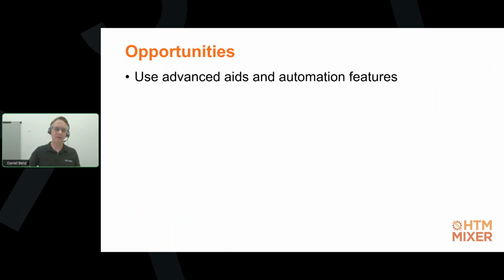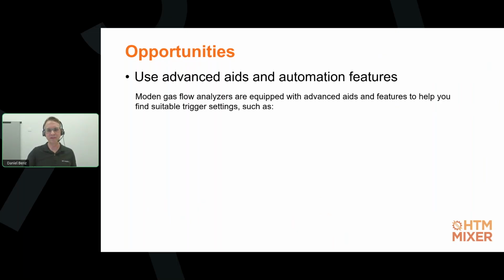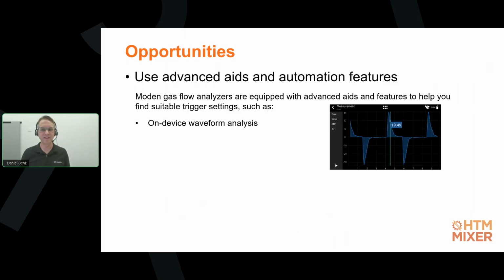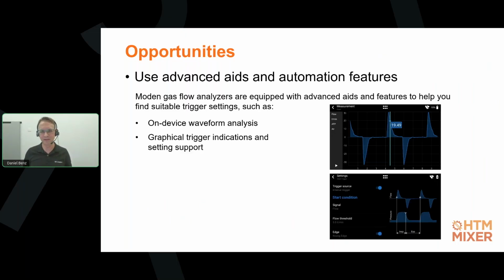Secondly, most modern gas flow analyzers offer valuable aids and automation features helping you to find suitable trigger settings for your specific application. So check if your gas flow analyzer has features like on-device waveform analysis, making it easy to determine the best trigger signal and trigger level, or graphical trigger settings indicators, as you can see on the screen here, to help you better understand what impact your settings changes are going to have on your waveform and where you're going to measure the levels.